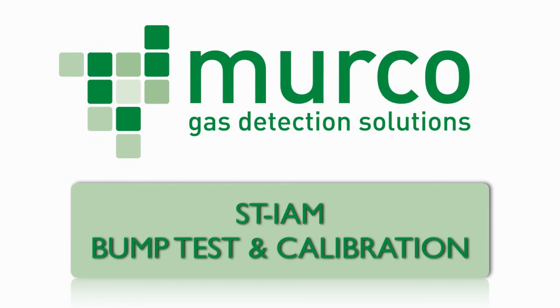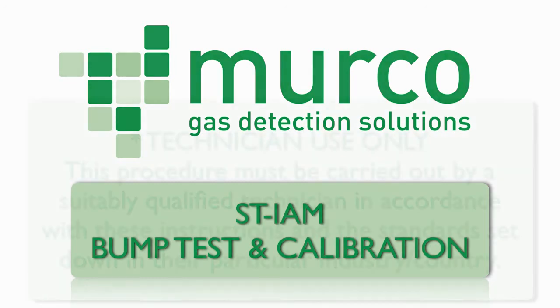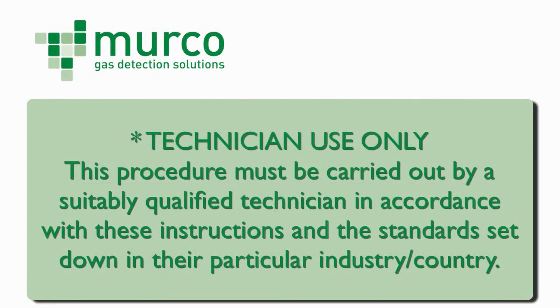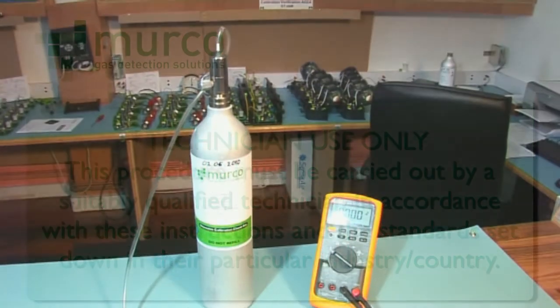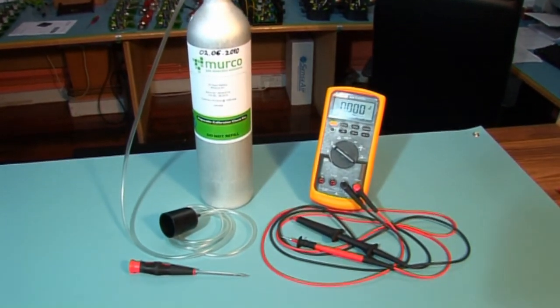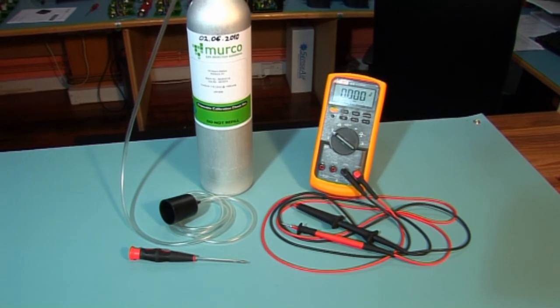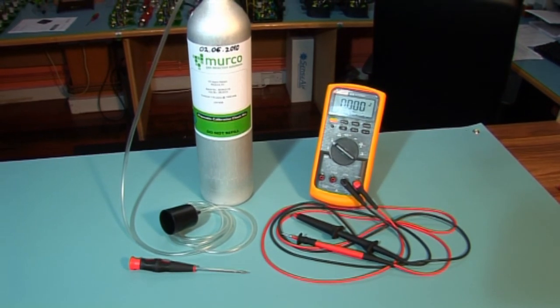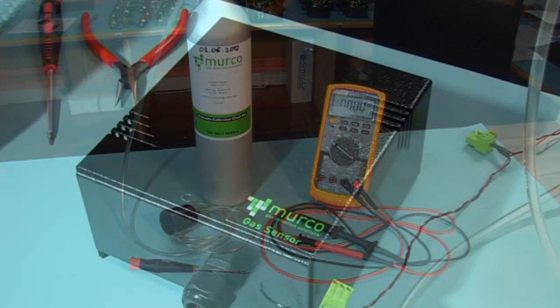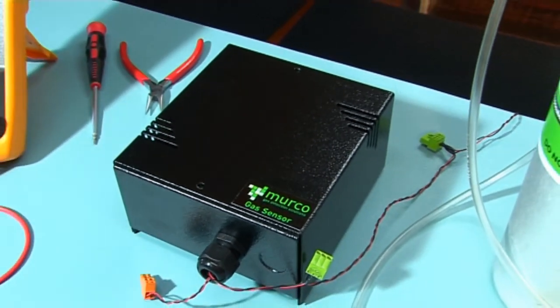The following procedure is a bump test and calibration of the ST-IAM unit. The tools required are a digital voltmeter with a resolution to 2 decimal places, a crocodile clip, a test probe, a flat-bladed screwdriver and a Murco Calibration Kit, which includes your cylinder of calibration gas, flow regulator, flexible non-absorbent tubing and a vented calibration hood. This is an ST-IAM unit.